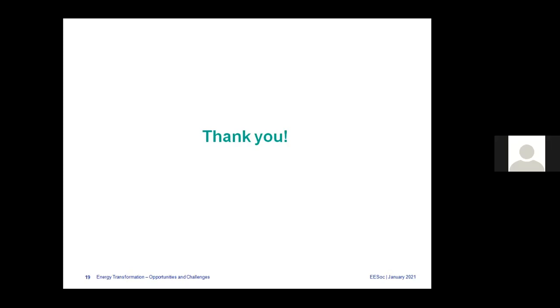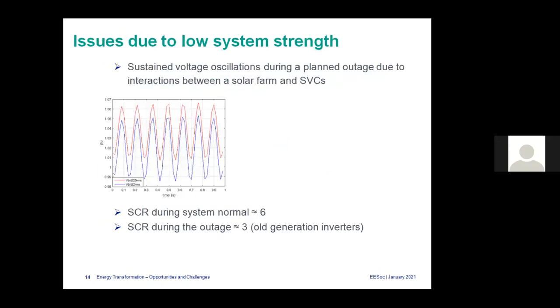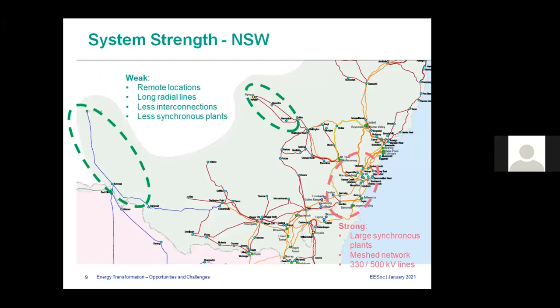Lots of curtailment. Like if you look at this slide, because in this area, for example, we have Balranald with about 450 megawatt of solar generation. At the moment, we allow only about 150 megawatt to generate at a certain time. Because this line is very long, about 250 kilometers. If you have more generation, the voltage will drop at Balranald below 0.9 per unit. So if there is a contingency on the southern side and one of these other lines trips, more power will flow through this 220 kV line, and it will drop the voltage further. So we constrain the generation significantly. Lots of generation constraints are applied during the day. Lots of solar generation, in fact, in this area, especially Western and Southwest New South Wales, to ensure system security.